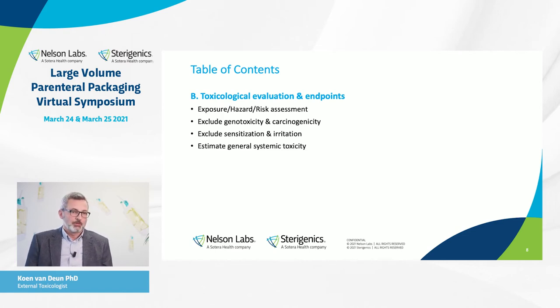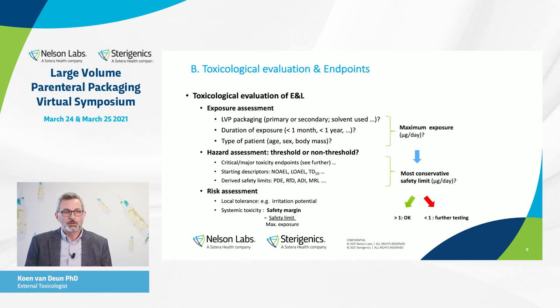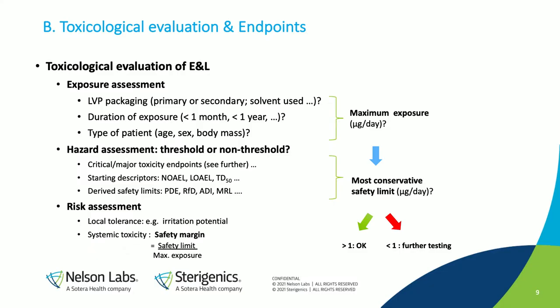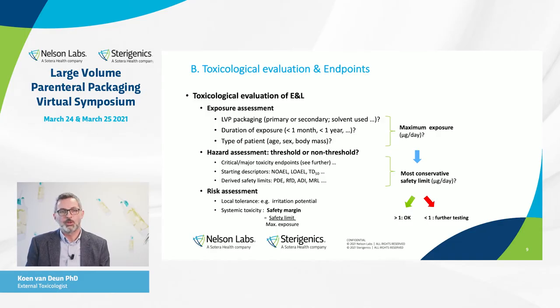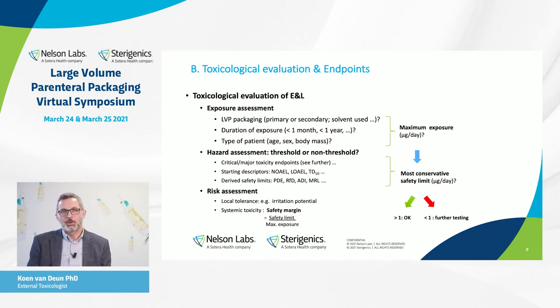Let's now look at the typical toxicological evaluation and which endpoints are the most critical. When we do a toxicological evaluation of extractables or leachables, we always start with the exposure assessment. We need to know what kind of packaging is used — is it the primary or secondary packaging, and what are the sources? This information is available in the analytical report, but it is important to know the origin of all the extractables and leachables, under which conditions they were found, which solvents were used, and whether they are more water-soluble or non-water-soluble, considering the typical end situation of the drug product.